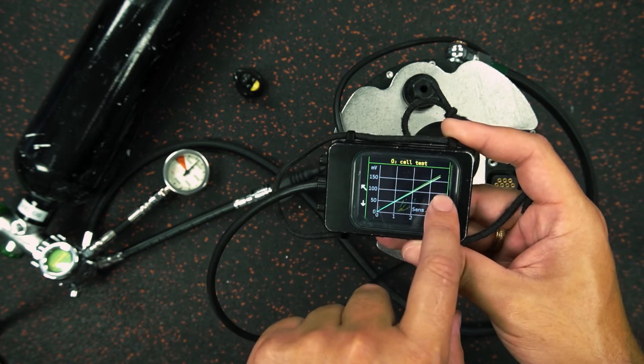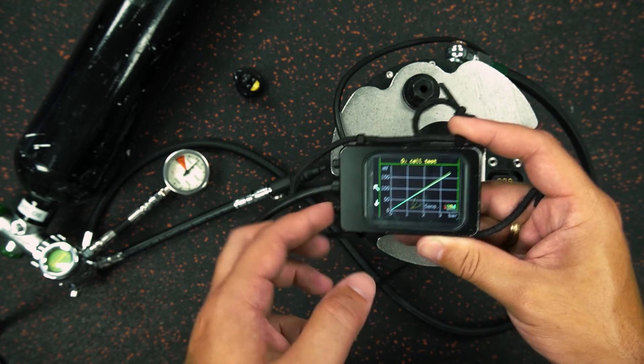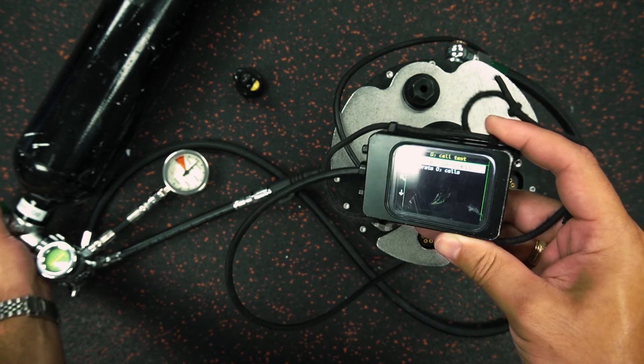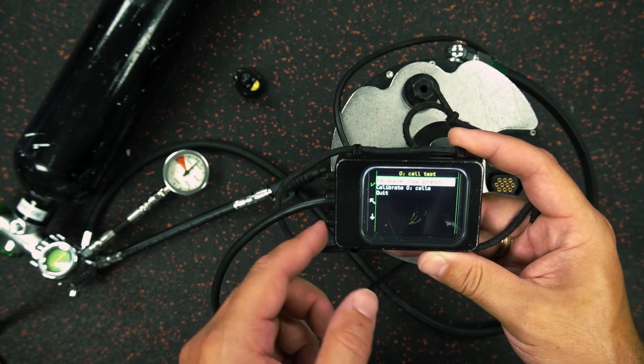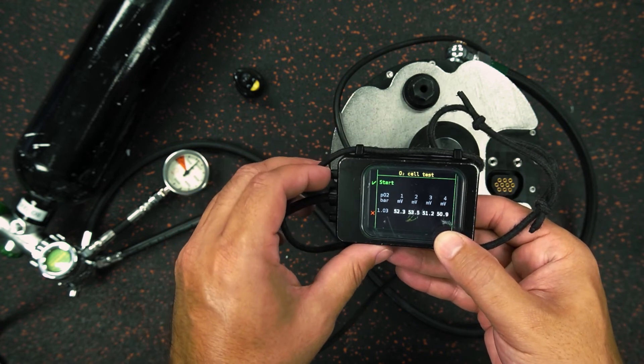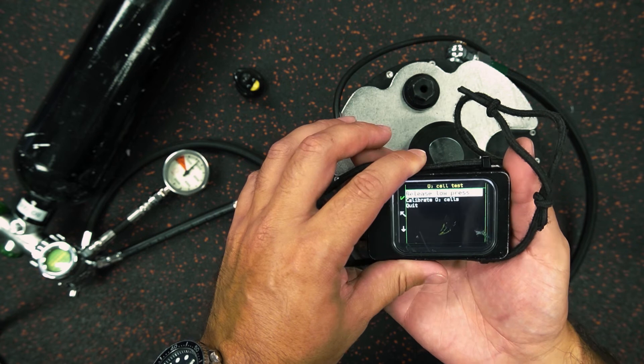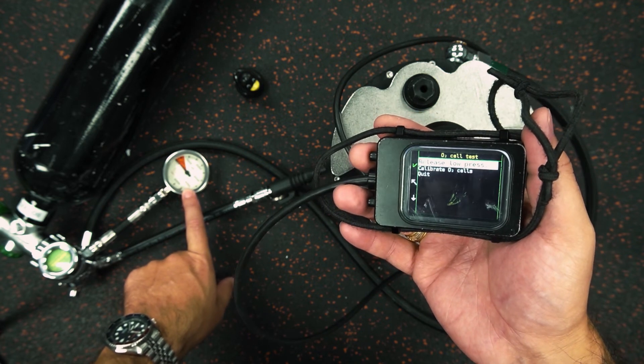Overall, this is a pretty good test — I'm very happy with it, but it does tell me that cell three I may want to keep an eye on over time. Now I push both buttons to scroll back and I can release the low pressure, shut off my oxygen, and begin to release the pressure. Something that's new and pretty cool with the new electronics is that one of these selections lets us calibrate our cells. I can go right to the calibration screen and get a very steady oxygen cell calibration with 100% O2. Then I can release the pressure and tell the system to release the low pressure from the solenoid while my valve is shut down, relieving the pressure in the line.